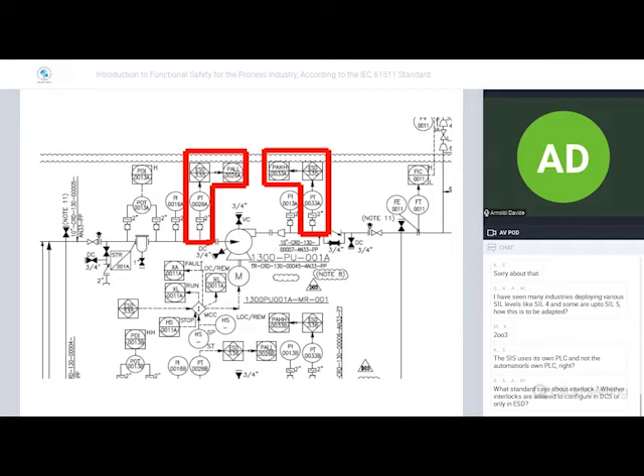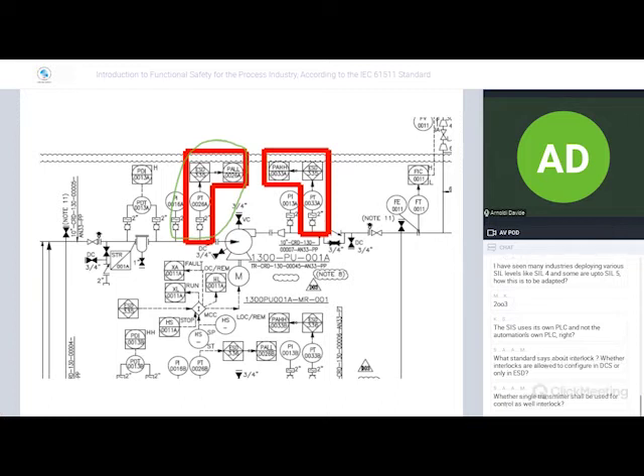In addition, to be sure to trip this pump by cavitation, we also include an additional function with an additional pressure transmitter. In case of low pressure, through the emergency shutdown system, we are going to disconnect the pump from the power, and so trip the pump. The same activation, so disconnection of the feed power of the pump, applies in case of high pressure.